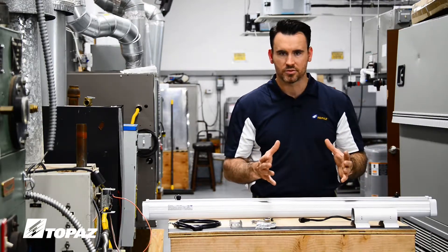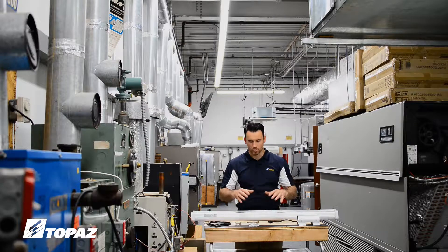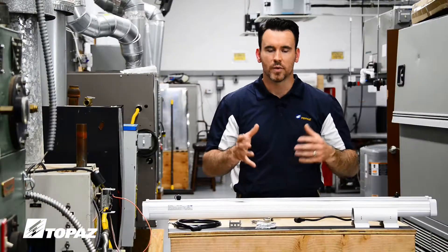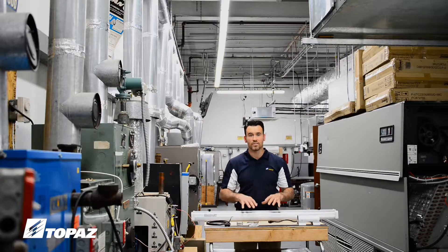It is major labor savings because it allows you to move much faster through your lighting installation. Here in this HVAC lab, we chose to install this four-foot fixture to upgrade our lighting. We had to find a lighting fixture suitable for the environment. When we install a lighting fixture, you have to be able to maintain your building. Our existing T8 light fixtures were maintenance heavy — changing ballasts, changing lamps. By switching over to this fixture, I was able to benefit from better lighting and lower maintenance. Today I want to show you how we chose to do the installation here at the HVAC lab.